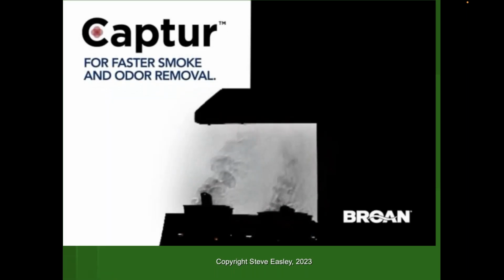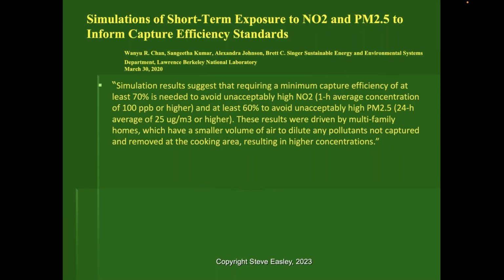So this is what you want your range hood to do. You want your range hood to be able to get both front and back burner capture efficiency for adequate removal of pollutants. And so I can't emphasize that enough. And when they looked at some simulations that they did, they found that the simulation suggests that requiring a minimum capture efficiency of at least 70% is needed to avoid unacceptably high levels of NO2, which is an average 1 hour concentration of 100 parts per billion. In other words, the outdoor limit for EPA is 100 parts per billion. So we don't want to go above the outdoor limit indoors, right?